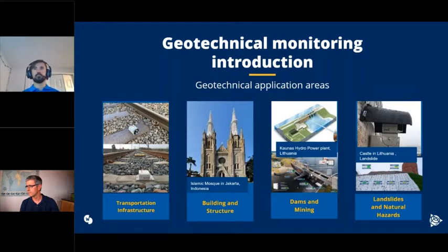So you're able to detect if there is overflowing. Also with a crack meter, you can detect if there is movement on a crack on a dam. And you can use Prism or GNSS. I think most of our customers use GNSS right now to have high frequency measurement on a dam. And you use Prism also to have the global displacement of the dam during a project.